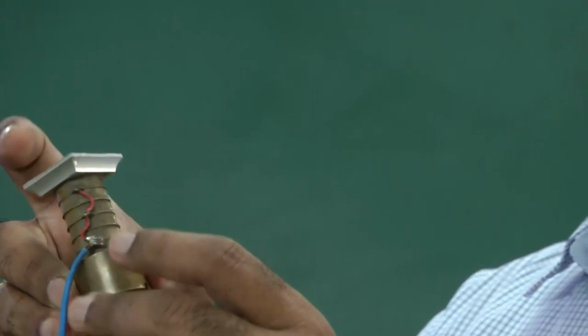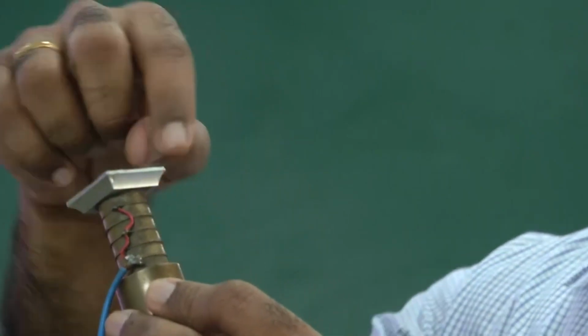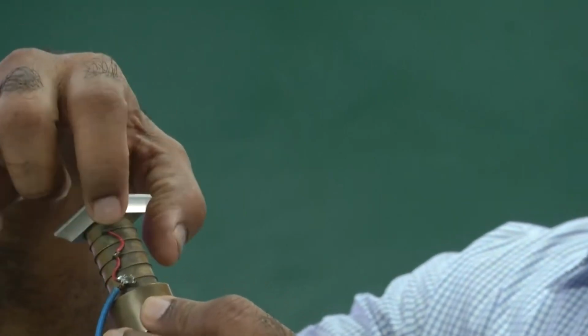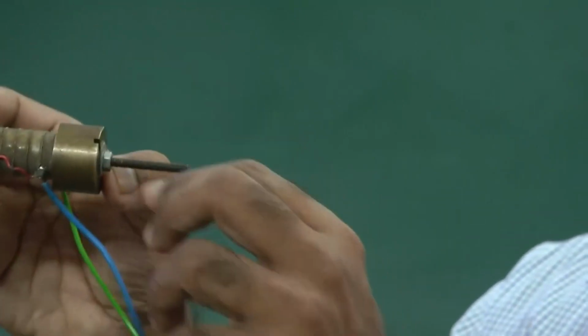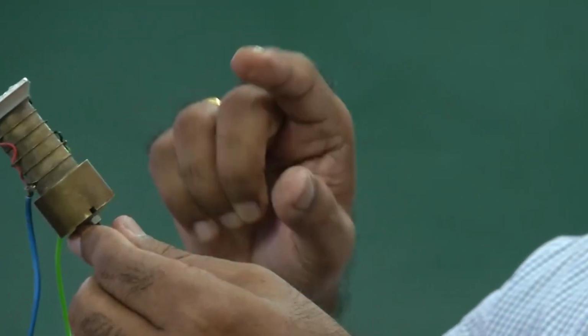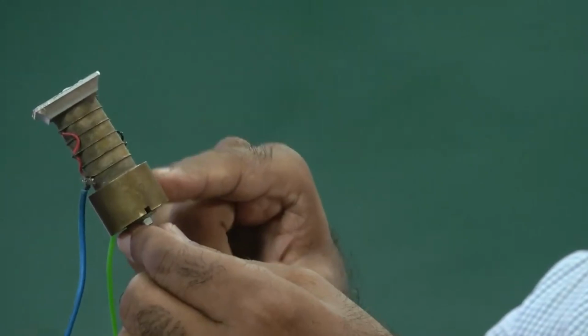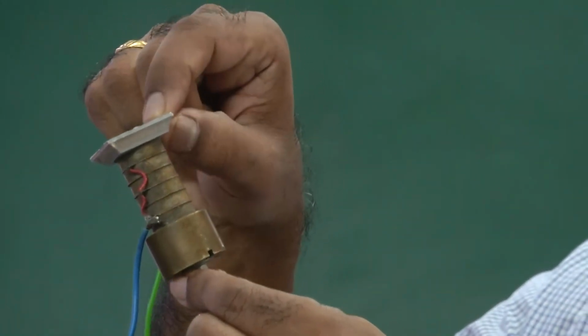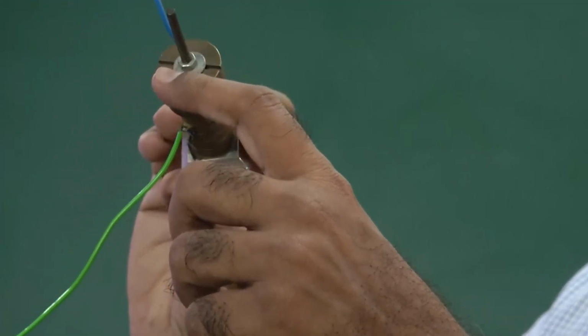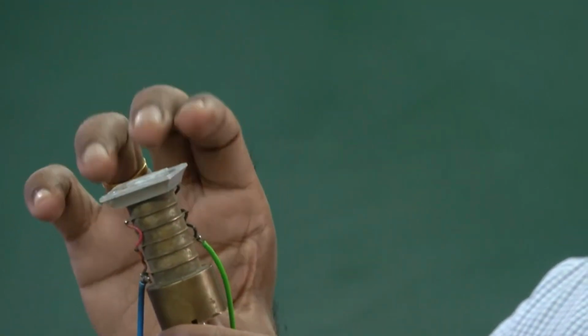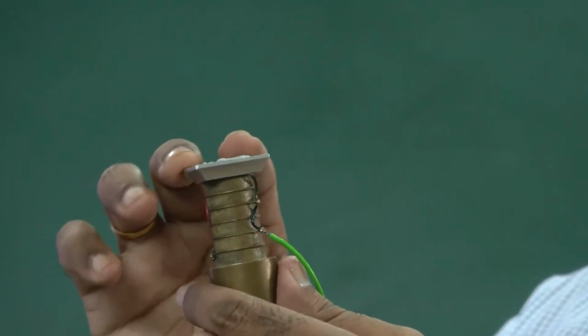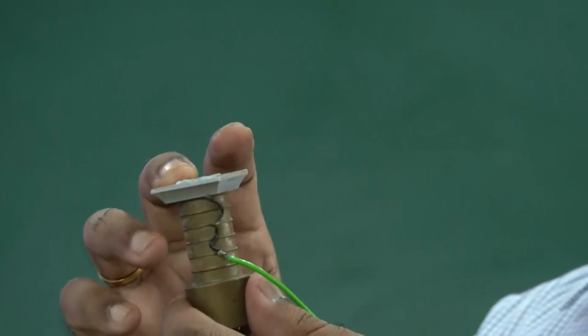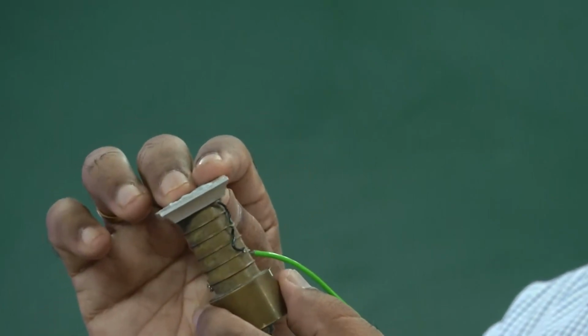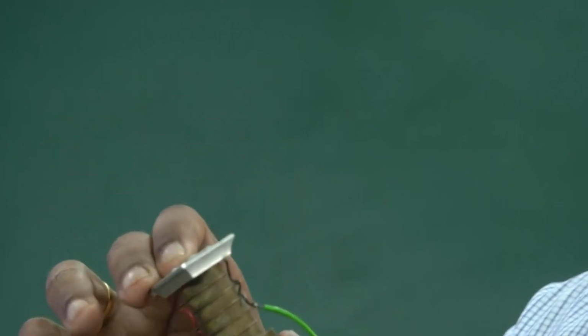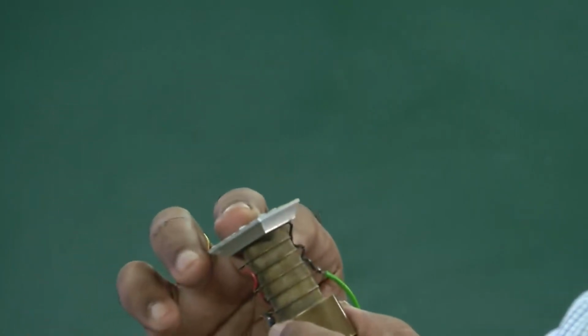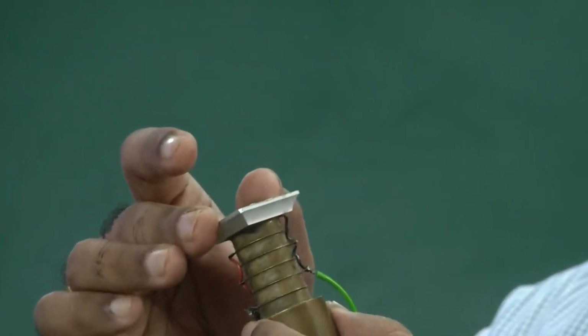Now, these discs are actually hollow discs. That means each disc has its own inner diameter and outer diameter, and through these discs passes this stress bolt. That bolt passes through the threaded hole in the tail mass, and the bolt is connected to the head mass. This nut, what you notice here, is going to be tightened so that these piezo discs are always in compression, and we learnt in the single degree of freedom forced vibration response that a typical accelerometer is nothing but piezoelectric material compressed using a proof mass, and as the mass vibrates, the piezo discs generate a charge, and that charge output is proportional to the acceleration that it records.